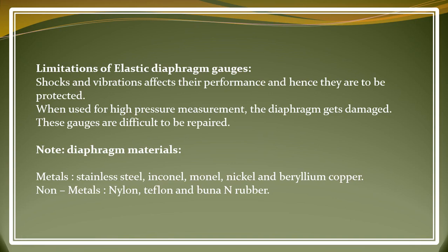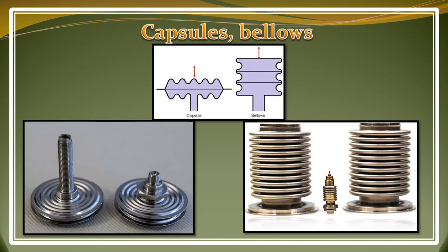And now here is a note about diaphragm materials. Let's read it. Metals, stainless steel, inconel, monel, nickel, and beryllium copper are used for metallic diaphragms. For non-metals, nylons, teflons, and buna N rubber are also used for non-metallic diaphragms.